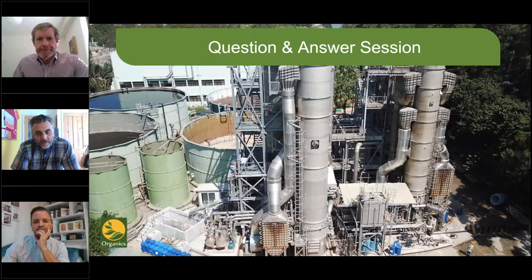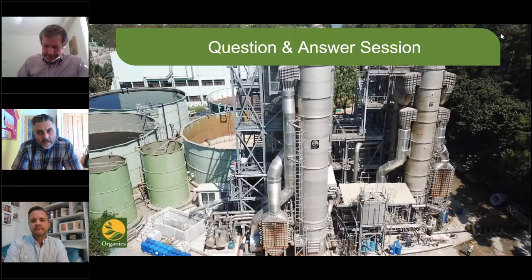Right, 1 hour. 1 hour, and that is when we use a lot of the heat recovery systems. Because we use a system of heat recovery to supply about 2/3 of the energy required, obviously on startup, there's no energy to recover. So you input about 1/3 of the required energy, and then you recover more and more. So the more efficient the system, the slower the startup, and we found about an hour is a sensible number. One of the earlier systems we did, when heat was not a problem, we could start it up in about 10 minutes because we had all of the heat available almost instantly by turning on the big button, and we generated steam within 5 minutes, and the system was up at temperature 5 minutes later. So it's a balance between recovery of reused heat and primary heat input for startup time, about an hour.